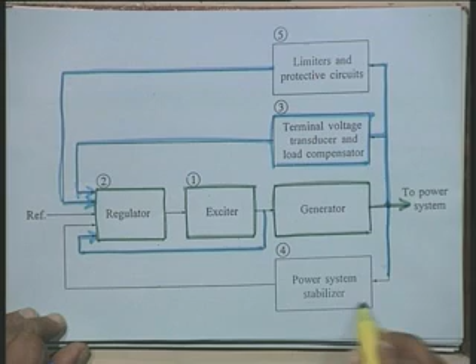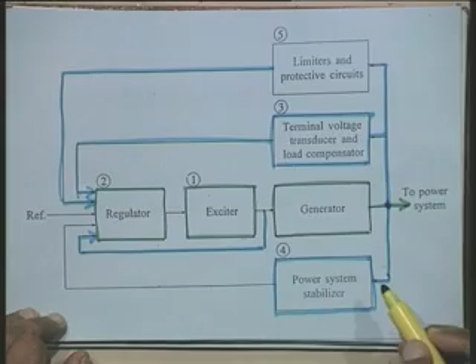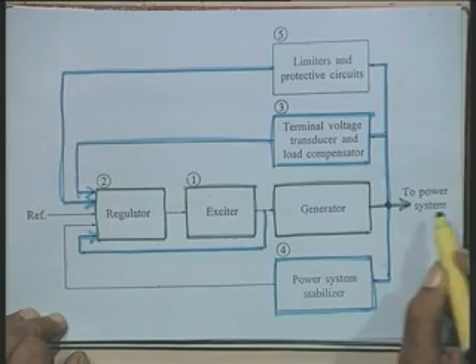And the last feedback loop is through the power system stabilizer. You can see this power system stabilizer. Again this power system stabilizer takes its input signal from the generator terminal. The input signal to the power system stabilizer is generally the speed deviation. When a synchronous generator speed deviates from synchronous speed, this deviation is sensed. Other signals which have been tried are the deviation in the power output. Instead of sensing the speed deviation, you can sense the deviation in the power output, the delta P e, or deviation in frequency has also been looked into, or a combination of these signals.